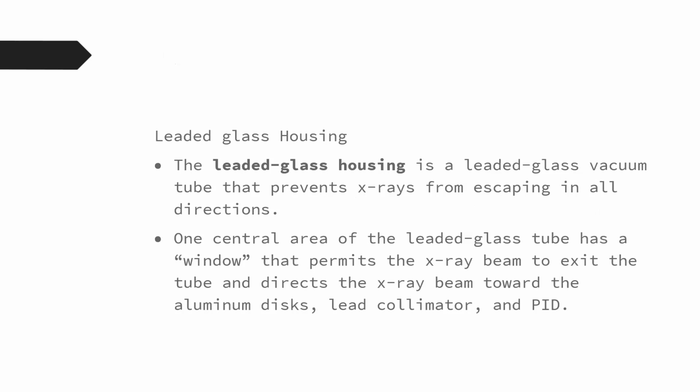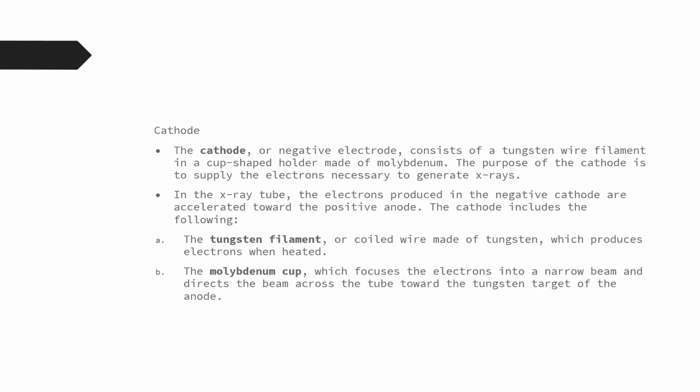And this is directed towards the aluminum disc, which filters the longer non-penetrating X-rays, and it exits through the lead collimator into the PID, all right?